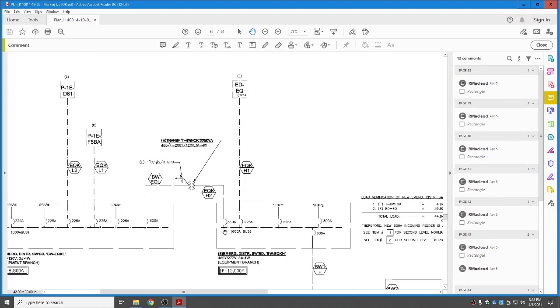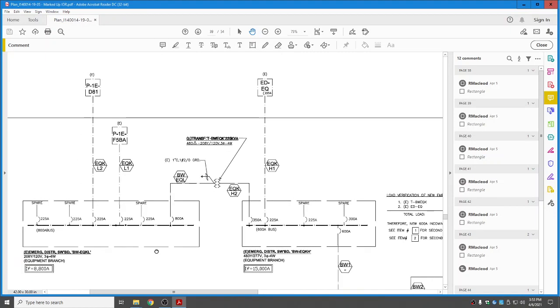Now also this equipment branch, you can see a 350 amp breaker. It comes up, goes to a transformer, which steps the power down from our 480 277 down to our 208 120 volt power. There's another ground that we need to have come off that transformer. This designates again wire size and conduit size. Comes down to this 800 amp bus.